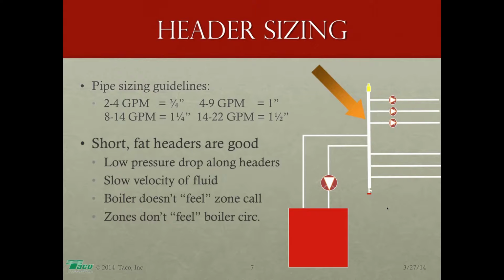In addition, if this is a retrofit boiler or a replacement boiler on an old system where you have a lot of cast iron radiators or baseboards and things like that, where after you've drained the system there's a lot of rust and crud in there, another benefit of a short fat header installed in this manner, we call this the charging moose. Short fat header installed vertically. By oversizing that header, what we're going to do is slow the velocity of the fluid through the header way, way, way down to less than 2 feet per second. We're going to really drop the velocity way down so that when the water comes back from the zones into the header, the crud and junk and rust that's in the water coming back from the system will drop down into that drip leg that you see, and you can actually drain it out. So it becomes kind of a dirt trap to keep that crud out of the heat exchanger of the boiler, and that's pretty important stuff.